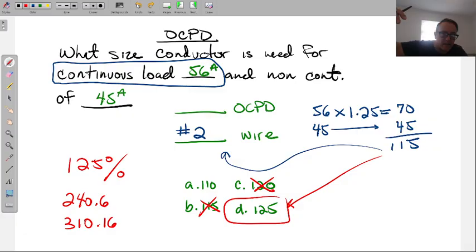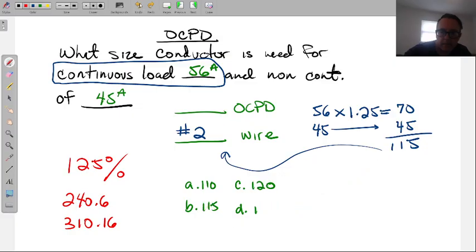Well, in the hundreds, I mean. The small ones, of course, there's 10 and 15 and 20, but in the 100s, the 200s, there's no 210, there's no 310, there's no jump over a 10 in the big numbers like that. I don't even know why it's there. I think it might have to do with motors or specific loads. But here we are. All right, let me just get rid of some of that. We don't need this. So yes, 125 now is our main breaker.